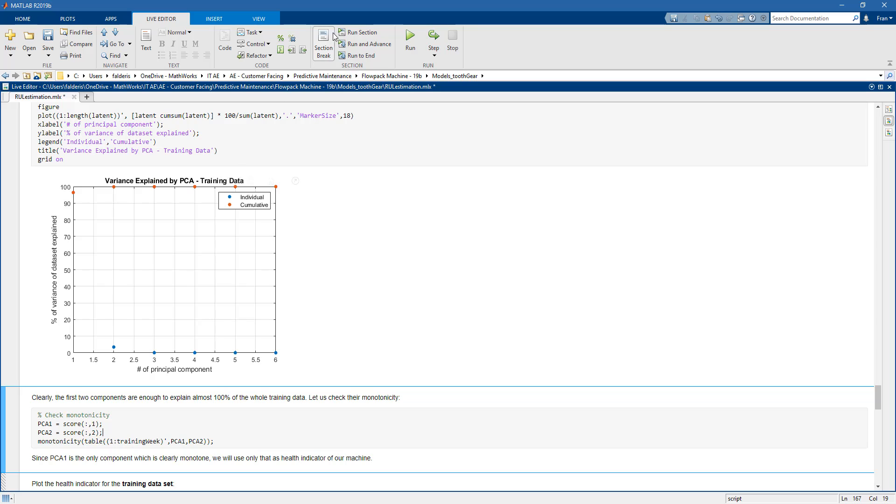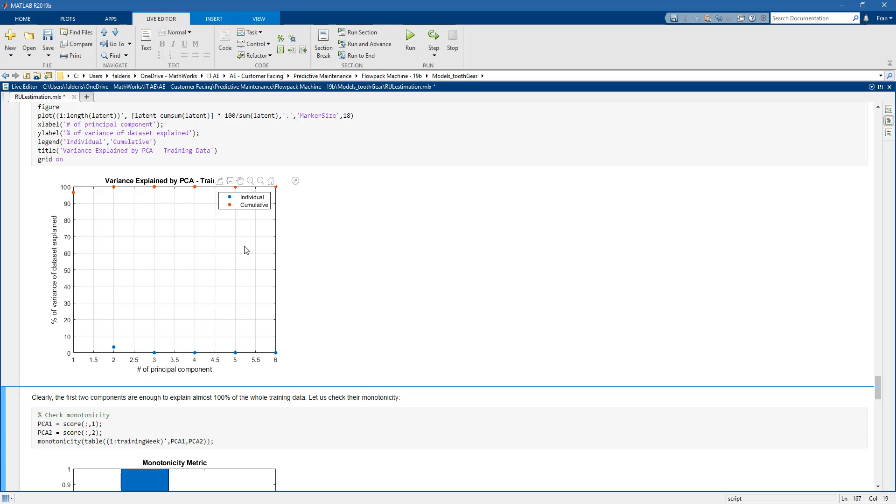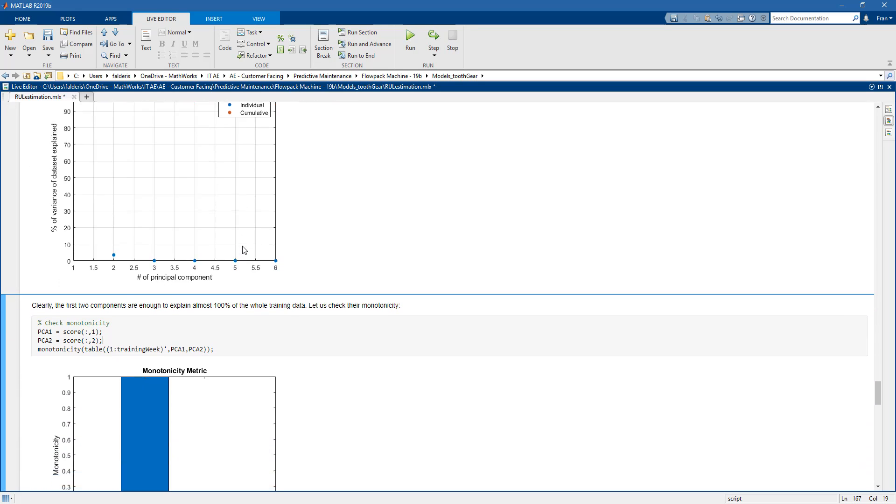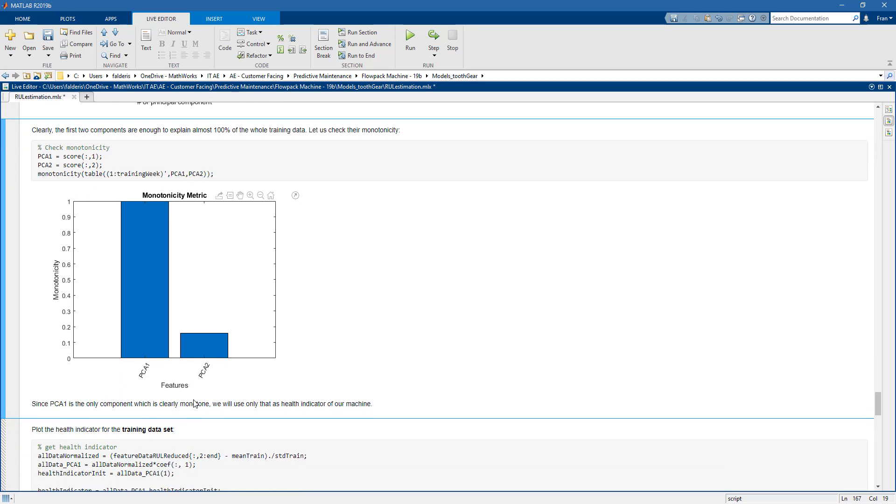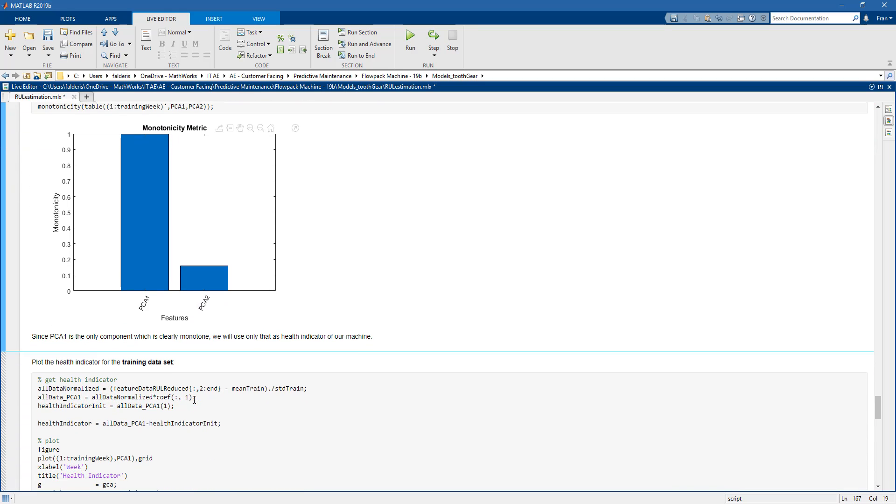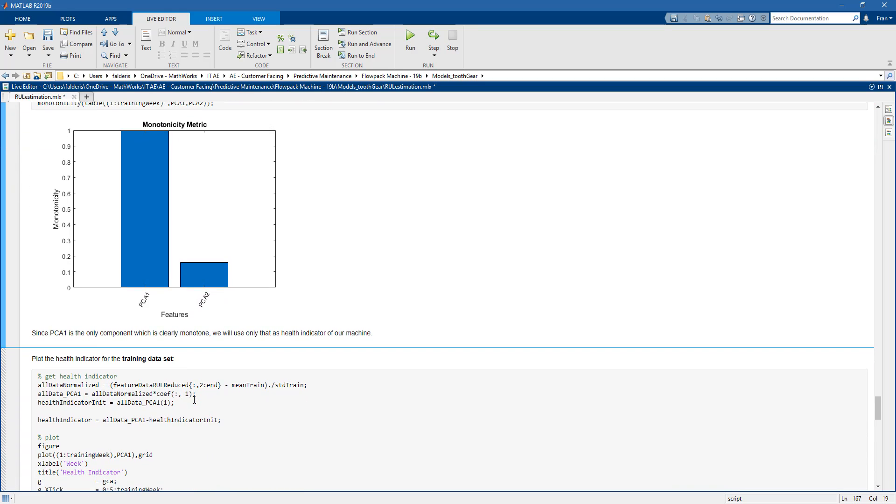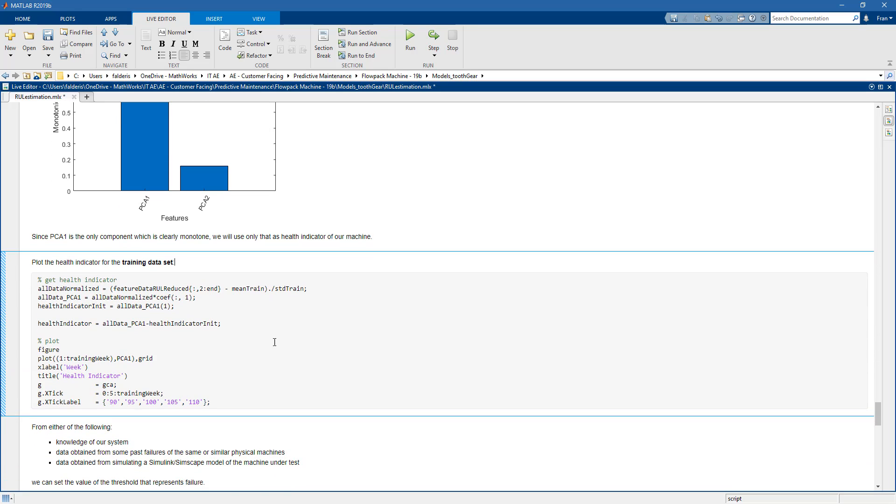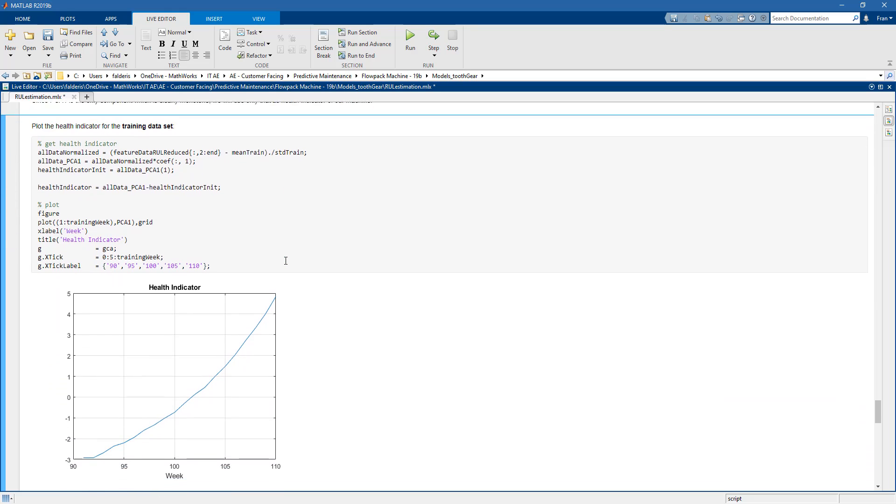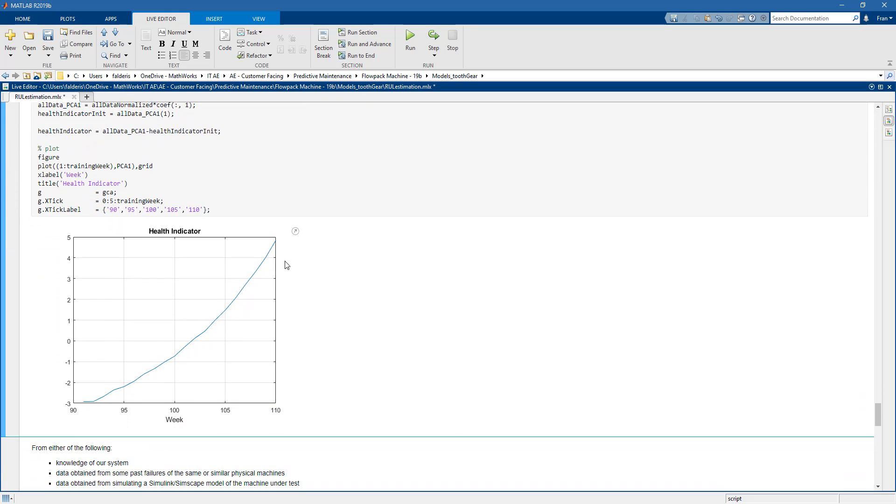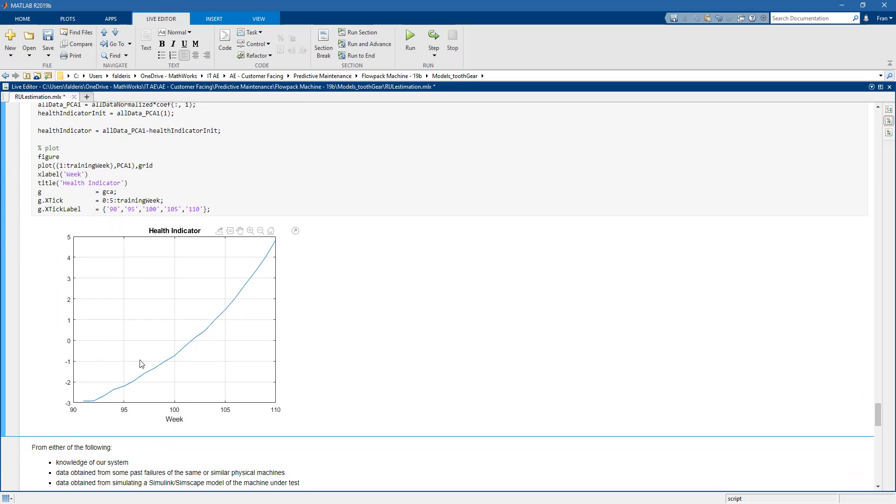So that means that maybe the first two principal components are enough to explain the data set that we have. Then we go on and we decide to check whether the first two components are actually both monotone. And what we see here is that only the first principal component is monotone. So summarizing, that means that we will use the first principal component as health indicator of our machine. And then if we plot the trend of this first principal component, we can see that as the number of weeks increase, also the health indicator increases.